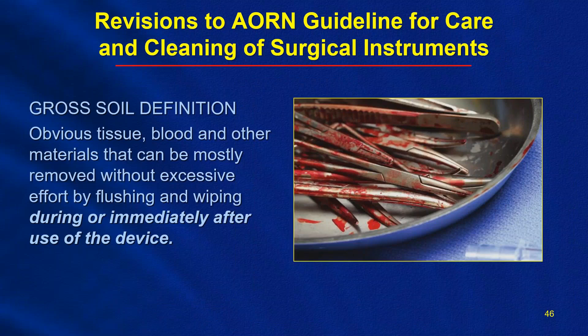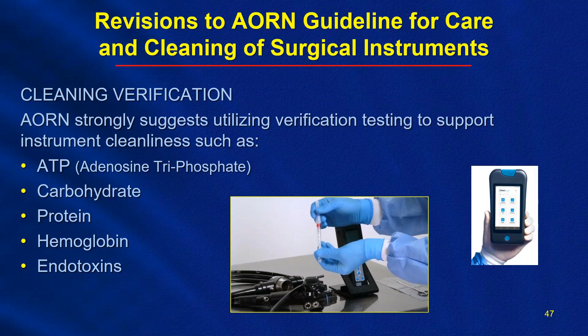Regarding cleaning verification, AORN strongly suggests utilizing verification testing to support instrument cleanliness, such as ATP testing, carbohydrate, protein testing, hemoglobin, and endotoxins. They're not saying which one to use or which one is better, but they strongly suggest, again, using some sort of verification testing to make sure your instruments are cleaned properly.